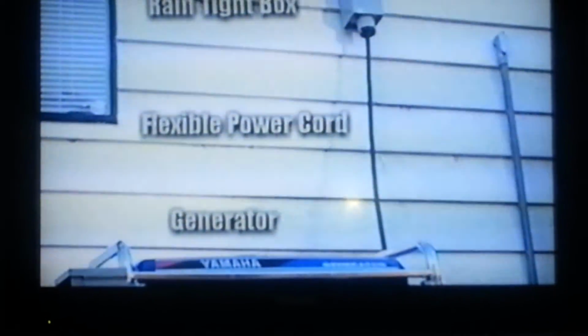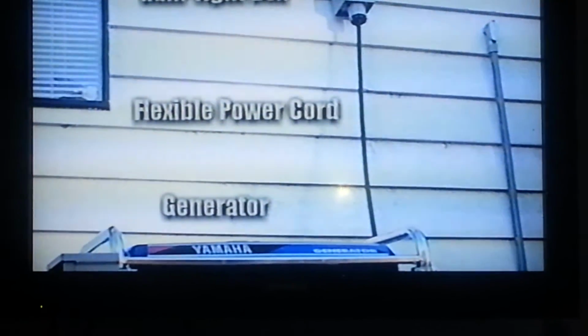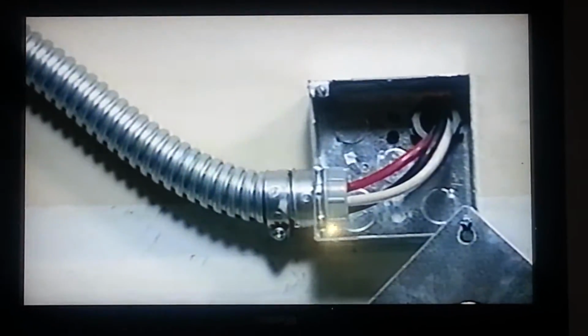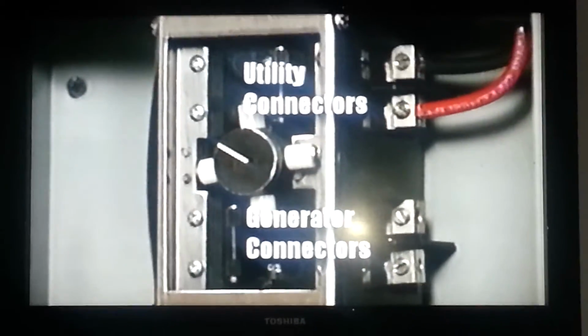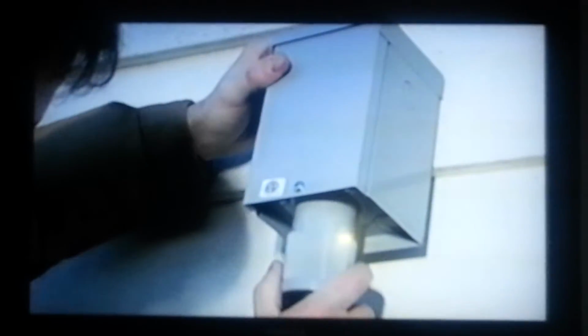Portable generators are often connected via a flexible power cord that leads to a rain-tight box on the outside wall of the building. To connect the ATS transfer switch to your portable generator, you should first run wires through a knockout in the right-hand side of the ATS transfer switch. Connect these wires to the generator connectors, located just below the utility connectors for the service panel, in the upper right corner of the transfer switch. Next, run these wires to the rain-tight box that is used in connecting to the generator. Connect the wires to connectors inside the rain-tight box according to its instructions.